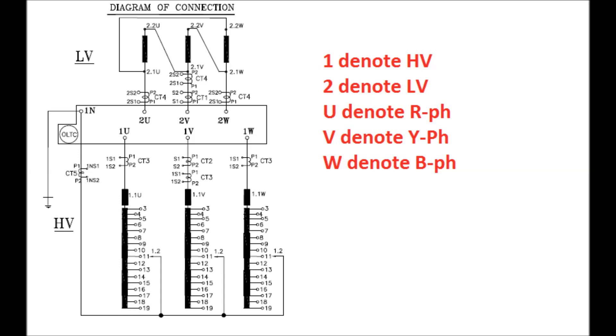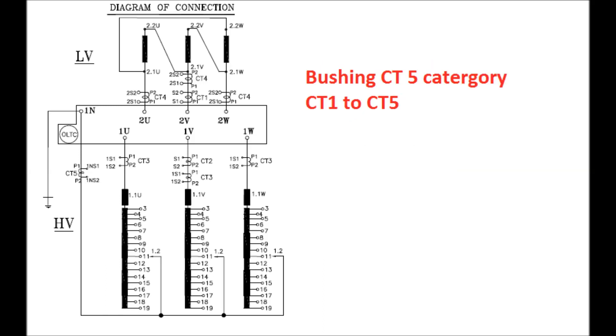A diagram is shown in the nameplate depicting the tap winding, HV side winding, and LV side winding. Terminals 1U, 1V, and 1W represent the HV side red, yellow, and blue phases respectively, and 1N represents the HV side neutral which is connected to earth. Terminals 2U, 2V, and 2W represent the red, yellow, and blue phases of the LV side winding. There are different bushing CTs shown in the diagram: CT1, CT2, CT3, CT4, and CT5, whose purposes will now be discussed.